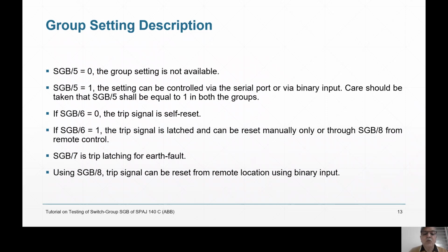If you make SGB 6 equal to 1, then the trip signal will be latched. It will be manually reset. And manual reset you can do using SGB 8 from remote also, from some control room, from somewhere else. And you have to give the binary input, right? So SGB 6 is for latching the trip signal. SGB 7 is also latching, but in case of earth fault; SGB 6 is for overcurrent, that is phase overcurrent, and SGB 7 is for earth fault. So from SGB 1 to SGB 8, different facilities are available.